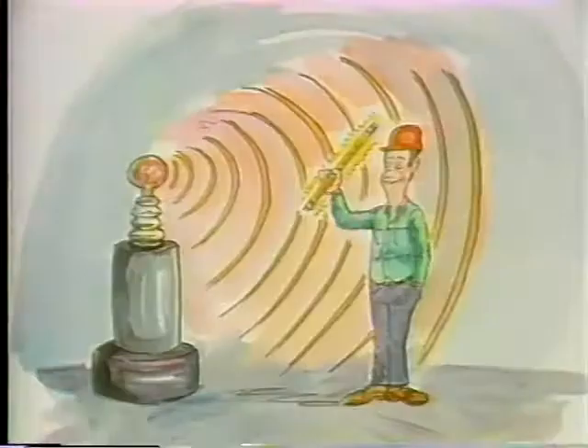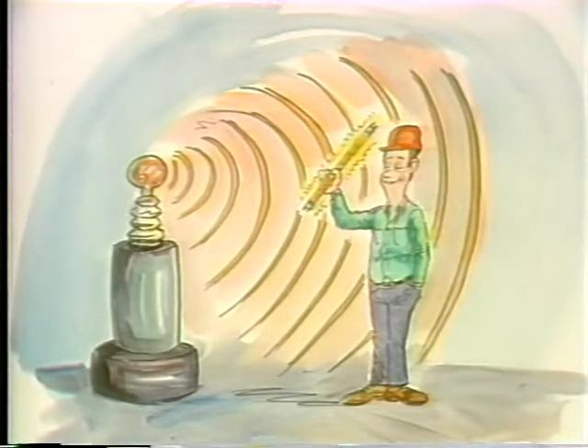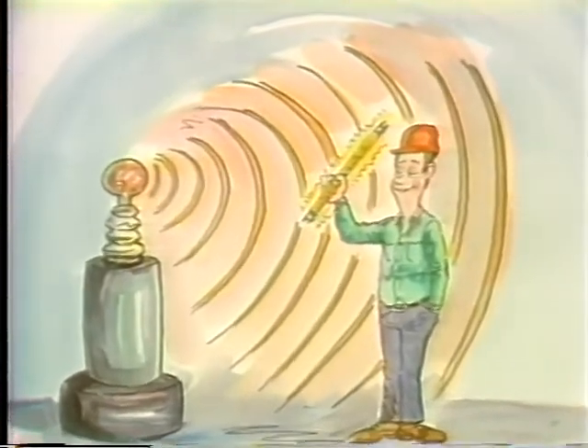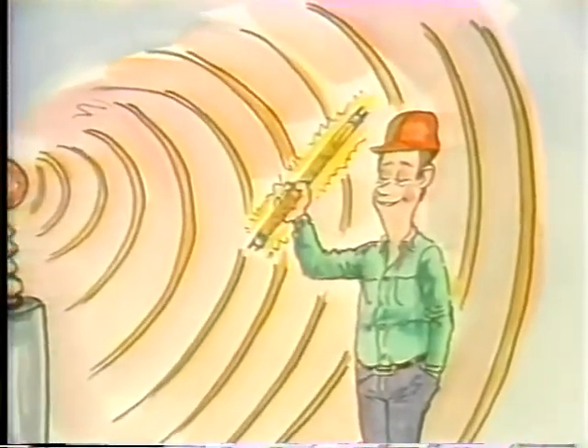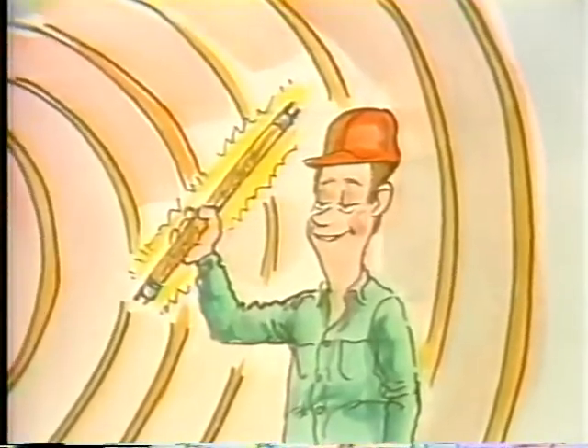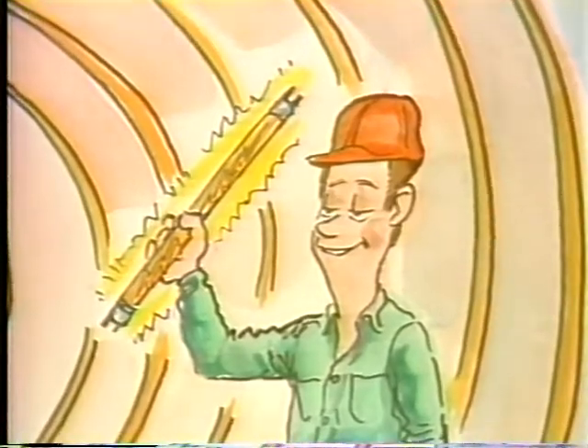The high voltage circulating in the coil induces current and voltage in the fluorescent tube. Even though the tube's not connected to the source, it's close enough to be charged up by the electrical field around the coil. Now, watch what happens when we de-energize the coil. The tube is still glowing. The capacitance of the fluorescent tube causes it to store a charge. It'll glow for a while and then slowly fade as it discharges. What you've just seen is an example of induction and capacitance. The electrical field surrounding the high voltage source induced a charge in the fluorescent tube, and the capacitance of the tube stored the charge. This has direct consequences for high voltage electrical maintenance.